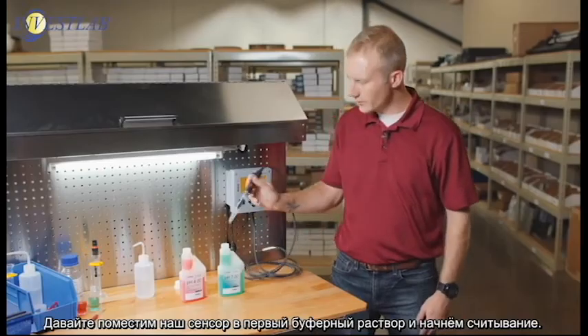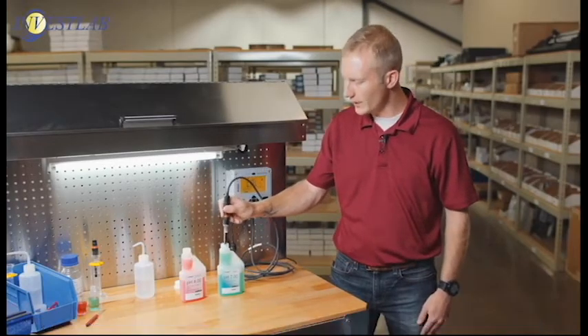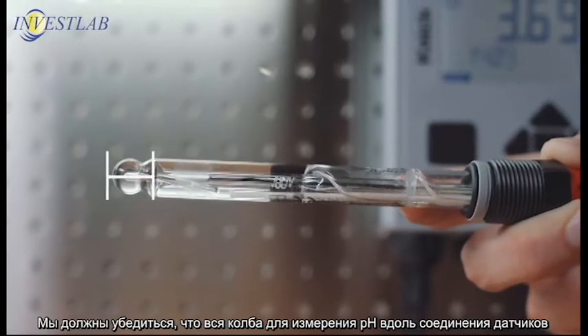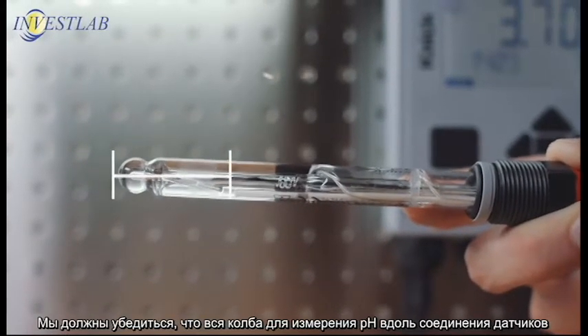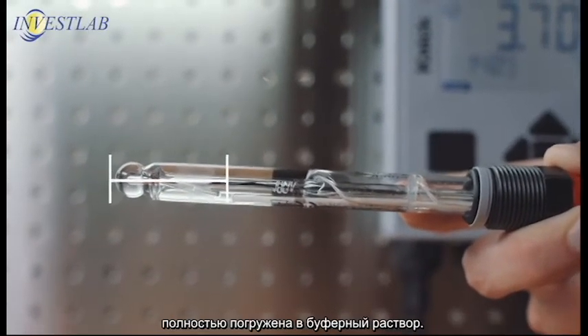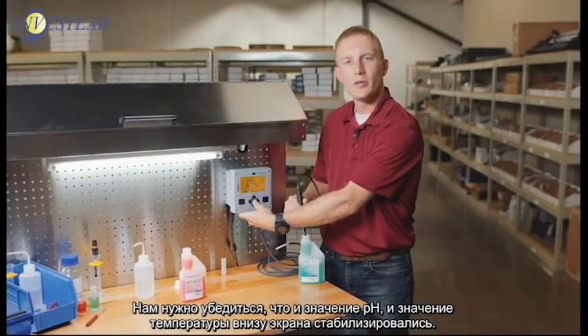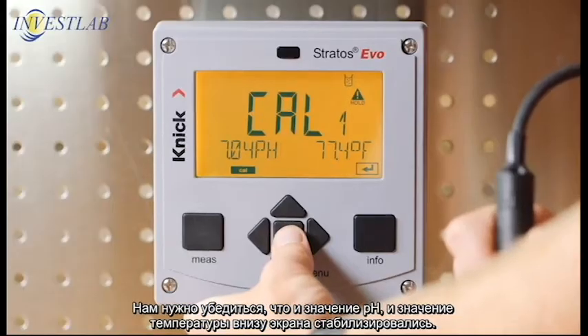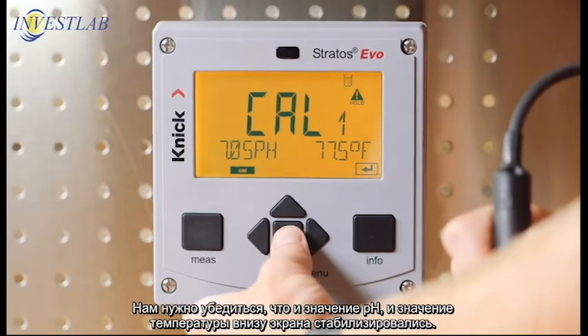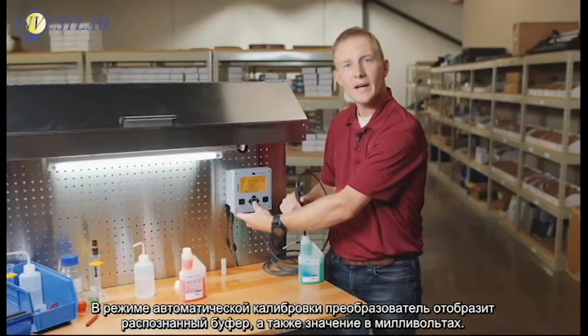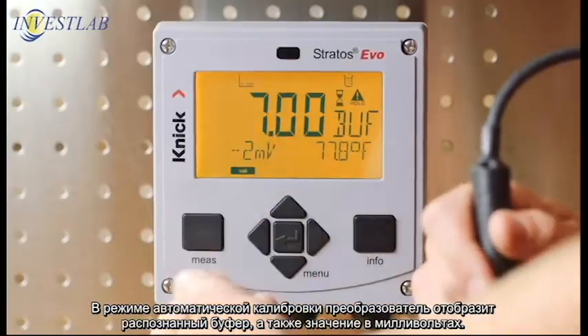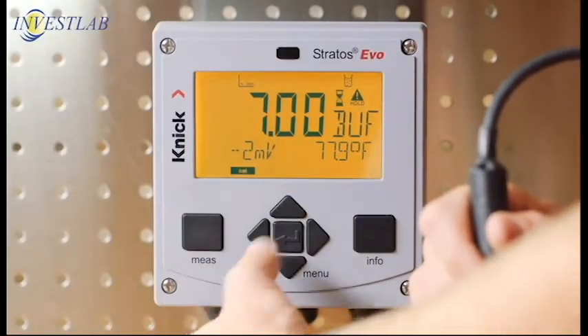Let's place our sensor in the first buffer solution and stir lightly. We want to ensure that the entire pH measuring bulb, along with the sensor's junction, are fully immersed in the buffer. We want to ensure that both the pH value and the temperature value at the bottom of the screen have stabilized. In automatic calibration mode, the transmitter will display the recognized buffer value as well as the millivolt value.